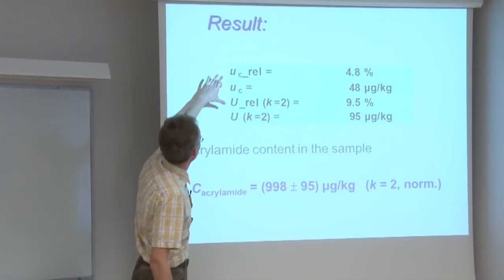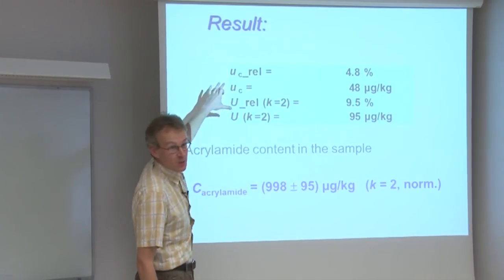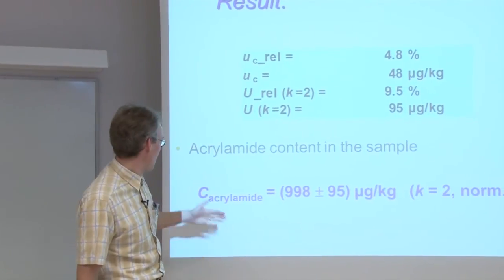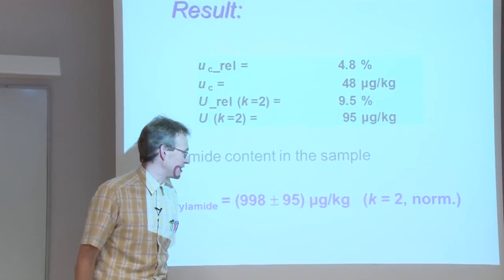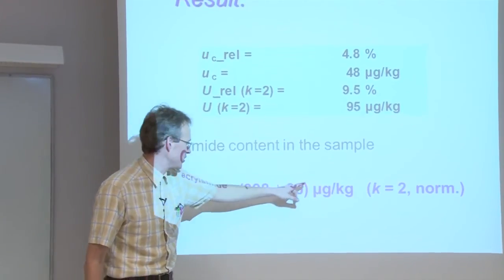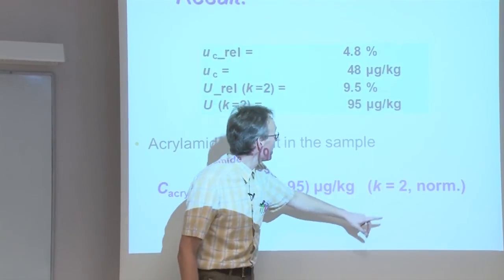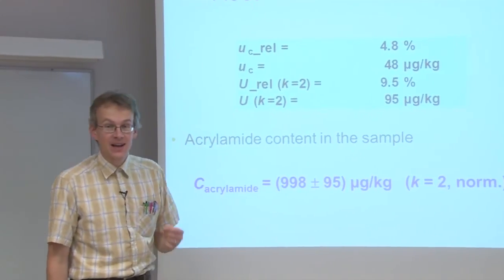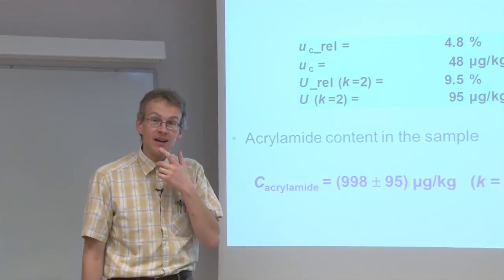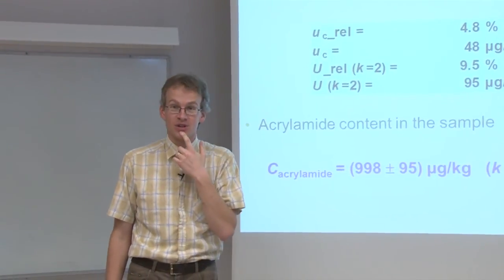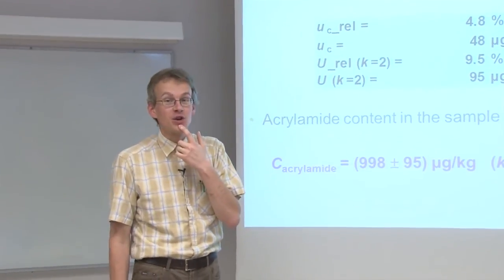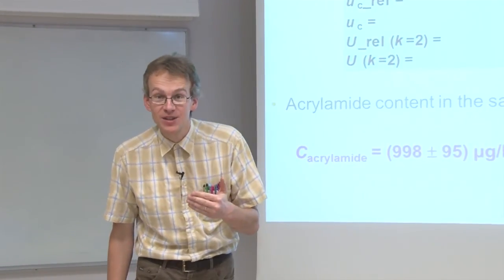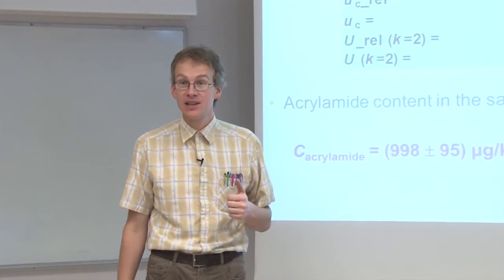This slide summarizes our measurement uncertainty calculation. The same uncertainties as calculated in Microsoft Excel are presented in different ways. The final result presentation includes: expanded uncertainty, value, unit, and coverage factor. I have also written 'norm' here, indicating normal distribution is assumed.